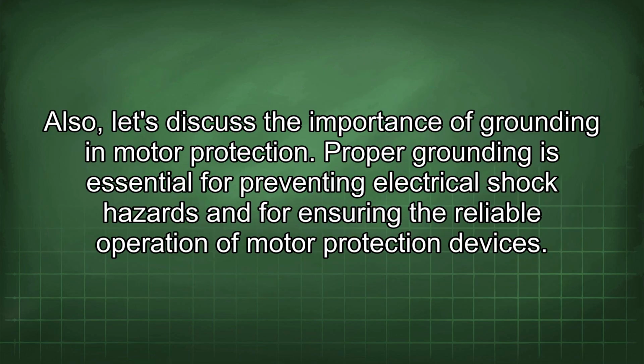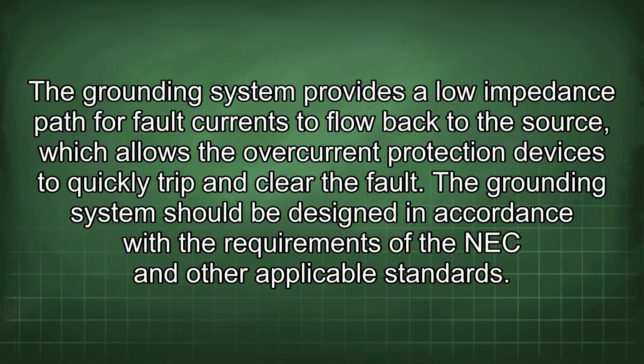Also, let's discuss the importance of grounding in motor protection. Proper grounding is essential for preventing electrical shock hazards and for ensuring the reliable operation of motor protection devices. The grounding system provides a low impedance path for fault currents to flow back to the source, which allows the overcurrent protection devices to quickly trip and clear the fault. The grounding system should be designed in accordance with the requirements of the NEC and other applicable standards.